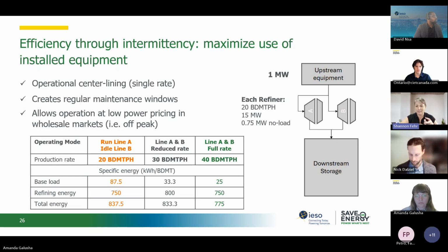An example shown in the diagram is a refining line, with two parallel refiners. These systems have chip feed equipment that draws load regardless of production, and refiners have large no-loads, the load to rotate equipment without production. Most mills also have downstream storage, and use of equipment and storage is predicated on equipment capacity and storage availability. If you have large no-load equipment but no storage, that could be an opportunity to justify storage.